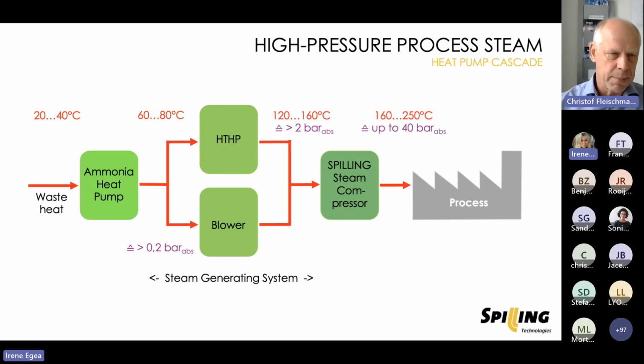In the middle temperature range, what is shown here in this slide, you see high temperature heat pumps, like they are now coming up, new innovative units, which are able to lift exhaust heat or heat from a 60-80 degrees Celsius level on their source side to above 100 degrees Celsius, up to 160 degrees Celsius.